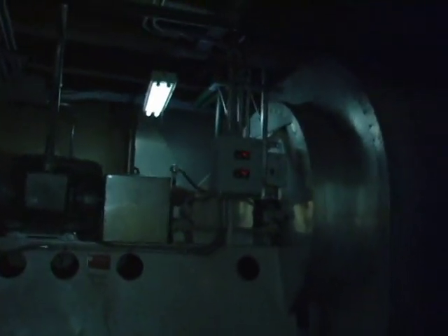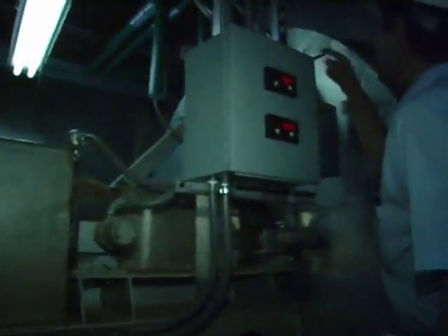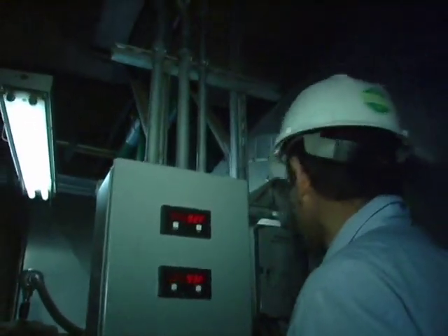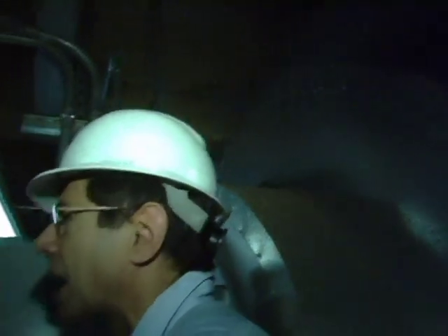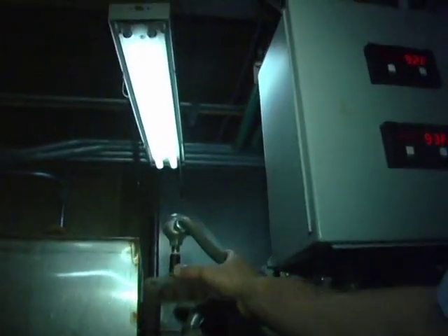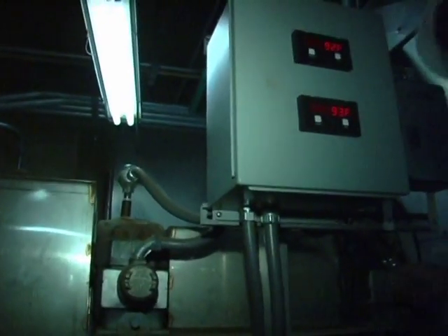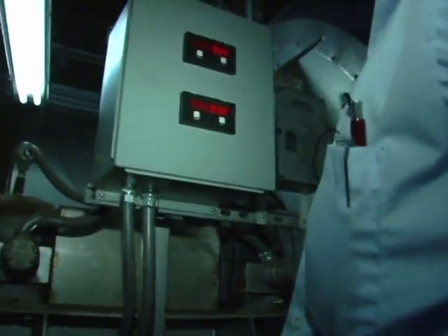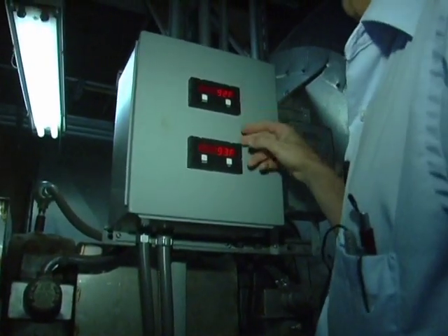This is the FGR fan. You can see it's a tight fit, wasn't it? Very tight fit. Here you got the temperature sensors on the bearings over here. This here, you see the water jacket coming in. The water's coming in over here for the water jacket. There's a water jacket to keep the shaft cool. Okay. There's a vibration sensor here, and that's a temperature sensor on each of the bearings. You got 1 and 2 over here, you got another one over here, and it'll keep track of those temperatures right here.